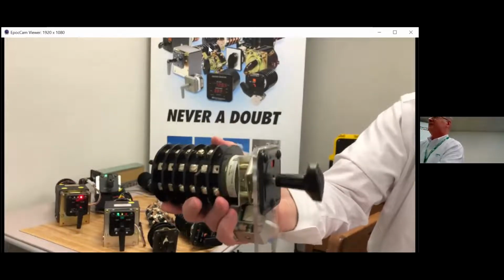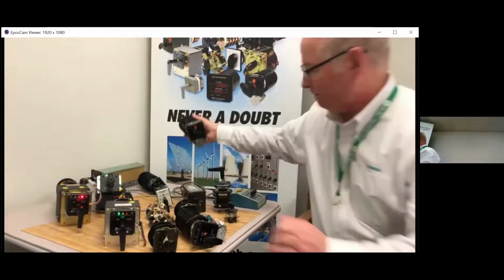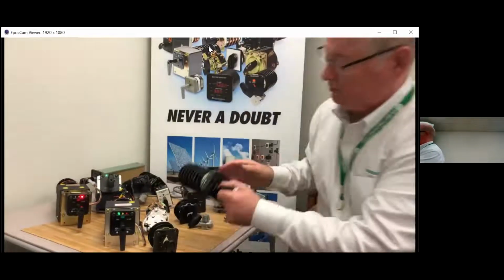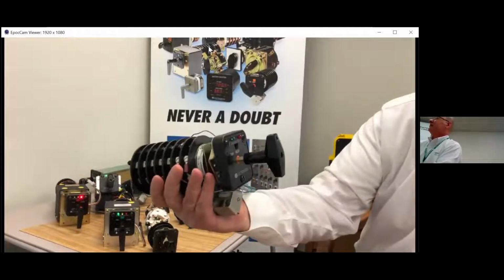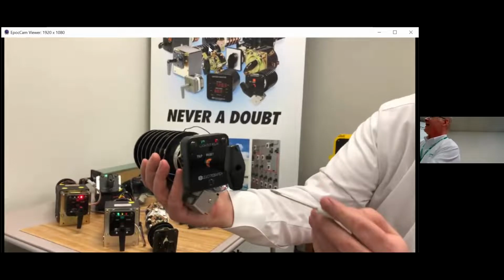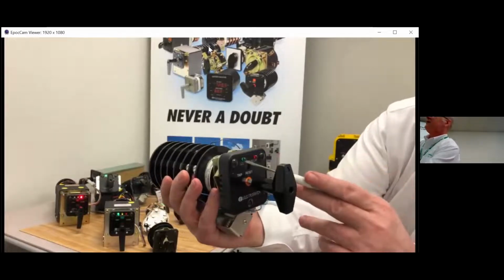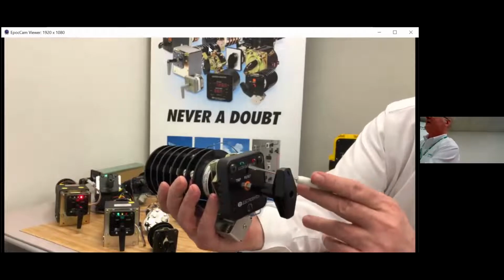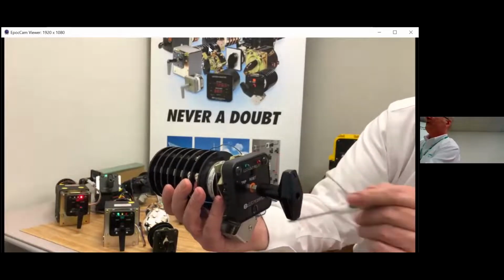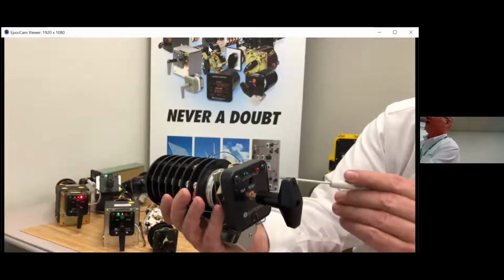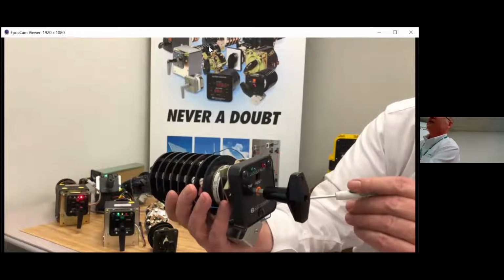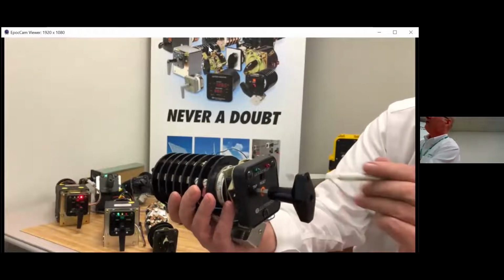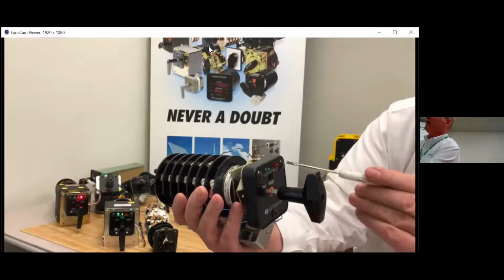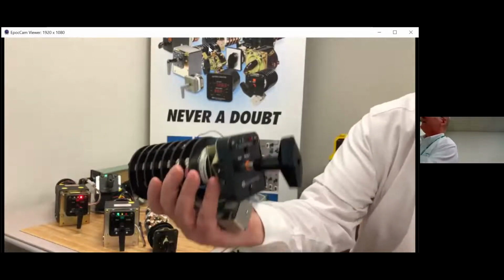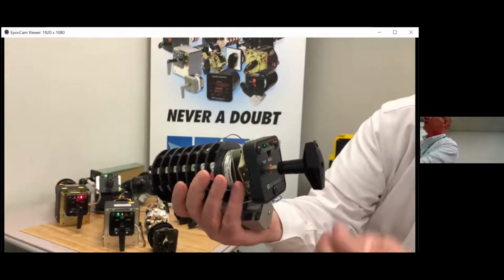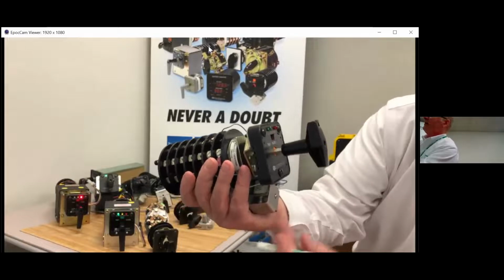Now, what we've been able to do with this design is to create a version that has a couple of things with it. One is it has the LEDs that specifically tell me that when the green LED is on, that means that the trip coil is healthy and I have current flowing to the trip coil, so the relay is ready to operate. And then when I do get a trip indication, or when I do get a trip, I have an LED indication that says I'm under fault, and it matches with the flag on the relay.